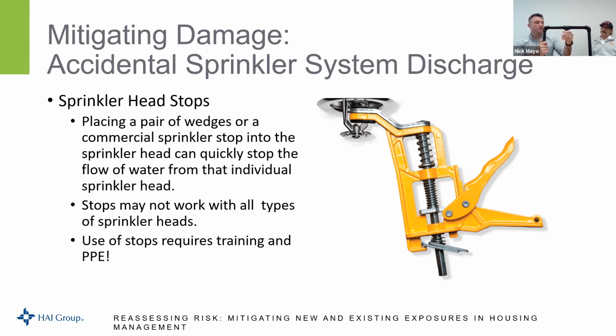There are different sprinkler heads for different applications. The sprinkler head will be in your sprinkler piping. It'll either be 1/2 inch, 3/4, or 1.25 inch piping. That bulb will be a color. The color will be dependent on the temperature at which the bulb will melt and fail for water to come out. As a fire department, if we come and this sprinkler head is activated and we want to stop the flow of water, let's say we can't get to an isolation valve, one thing that we may do is come in with a pair of wooden chocks and wedge them into the sprinkler head so that it slows down the flow of water.